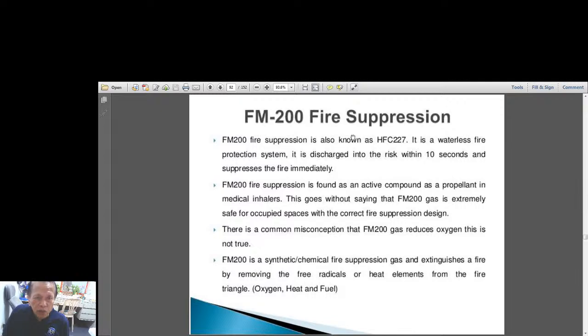So the FM200 fire suppression is also known as HFC227. It is a waterless fire protection system. It is discharged in the risk within 10 seconds and suppresses the fire immediately. FM200 is found as an active compound, as a propellant in medical inhalers. This goes without saying that FM200 gas is extremely safe for occupied spaces with the correct fire suppression design. There is a common misconception that FM200 gas reduces oxygen. This is not true. FM200 is a synthetic chemical fire suppression gas and extinguishes a fire by removing the free radicals or heat elements from the fire triangle. That means the oxygen, heat, and fuel.